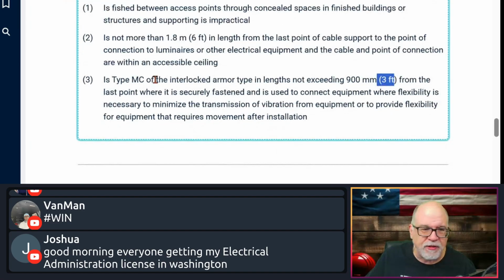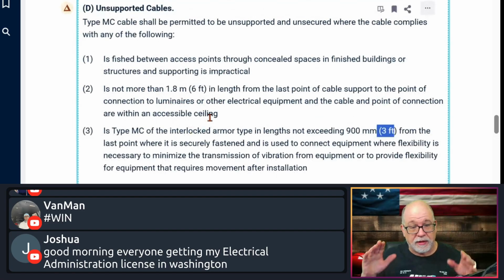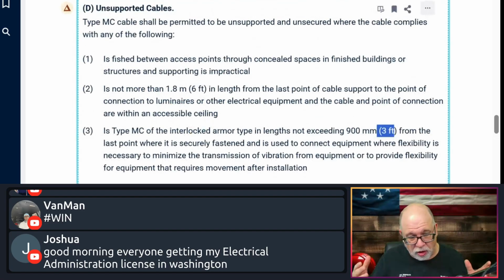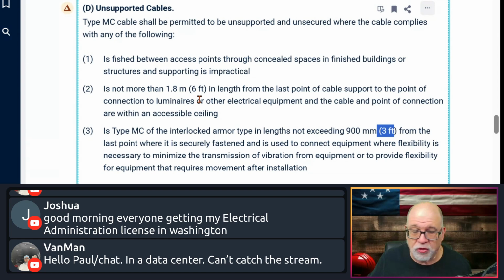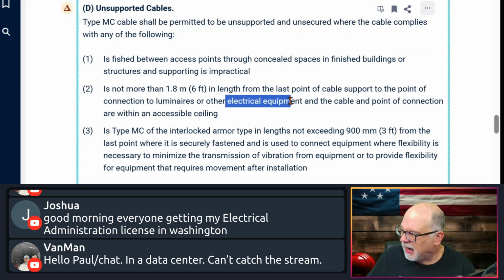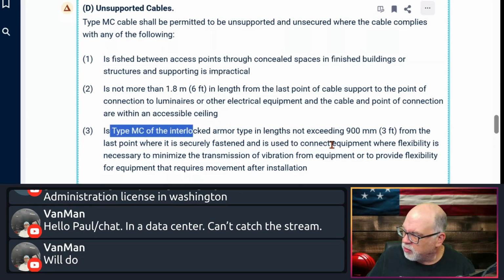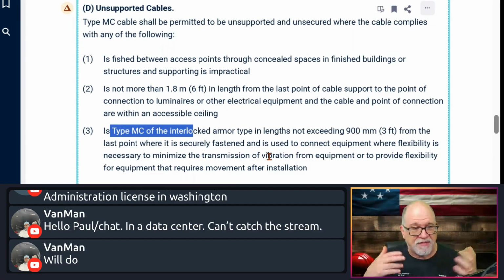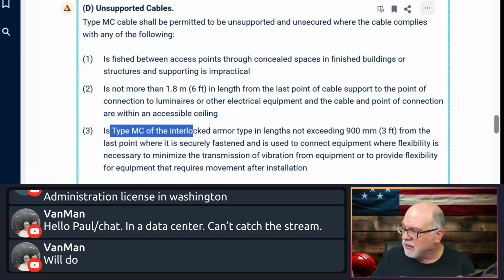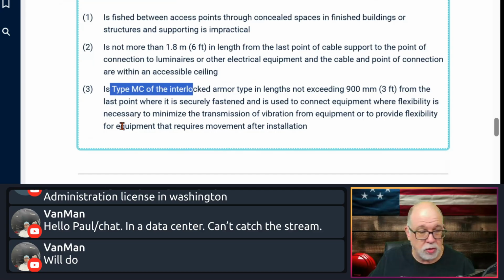So now what's the difference in these two? People say, because, you know, people are getting attention deficit disorder. The difference is 6 feet to luminaires or electrical equipment. And then with MC interlocked, you have 3 feet for other types of applications where things may move, may have vibration, flexibility is necessary. So we're reducing the length down. The luminaires and things like that are not going to move in the ceiling. You know what I'm saying? Shouldn't move in the ceiling.